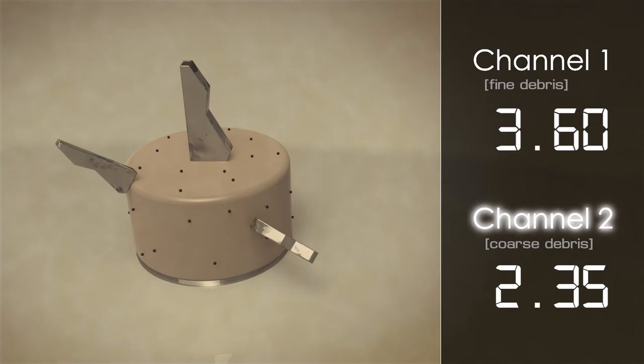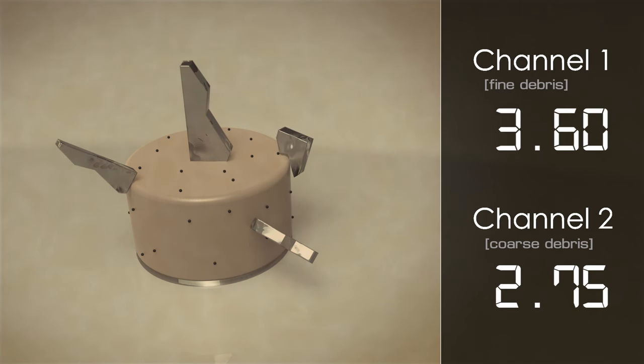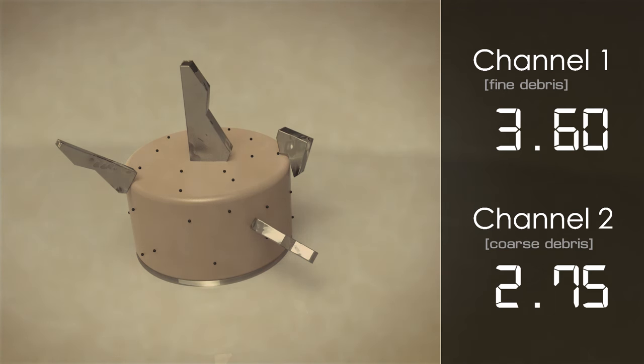The second channel, referred to as the coarse channel, is configured to monitor the build-up of larger pieces of metallic debris. Such pieces are typically present following a mechanical failure, for example a gear tooth breakage in a transmission system.